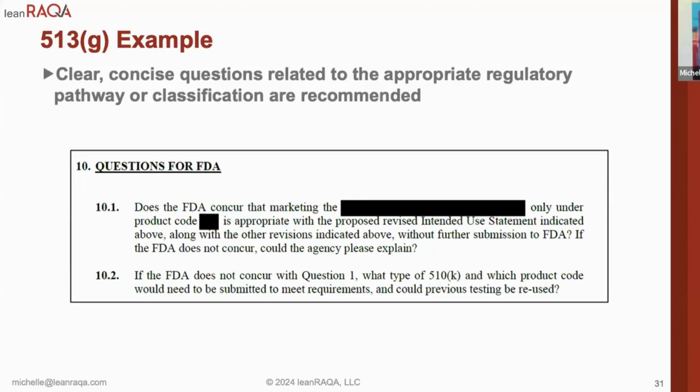So here we pose the questions with some context and a little bit more of a statement, and then ask, do you concur? If the FDA does not concur, what type of 510K and which product code would be needed to submit to meet the requirements?